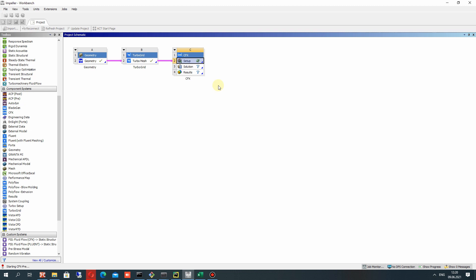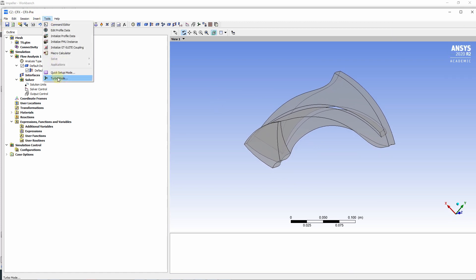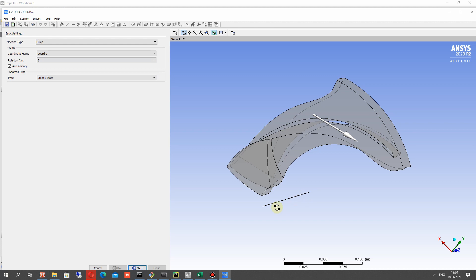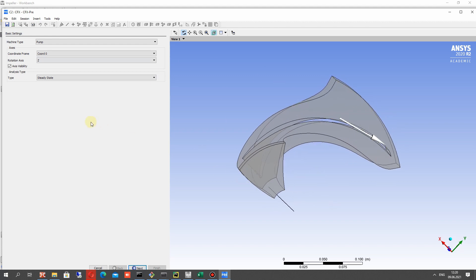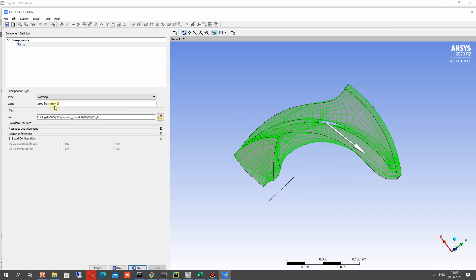Let's open CFX. In CFX we have to set up boundary conditions for the simulation. We can set up boundary conditions in Turbo mode, which is faster. Choose the pump machine type, set the coordinate axis of rotation to Z, and set the analysis type to steady state. Let's choose our rotor domain and set the rotation speed of the pump impeller.